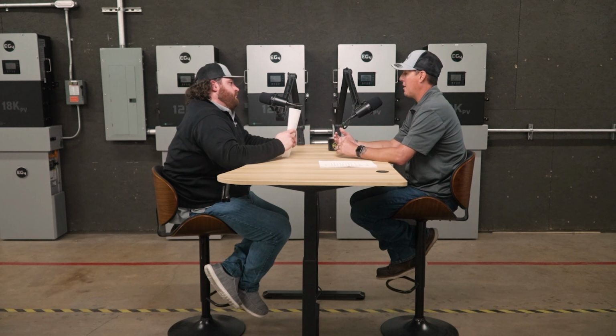You've got your utility input. If you wanted to make that your first form of disconnect, you could. You could throw that 200 amp breaker, whatever your service rating is, 100, 150, 200, and utilize that as your utility disconnect at the site without having to worry about adding all these additional AC disconnects. Getting into multimeters, whether it's an RGM or revenue grade meter for bidirectional sell-back rates, consumption versus production, stuff like that.